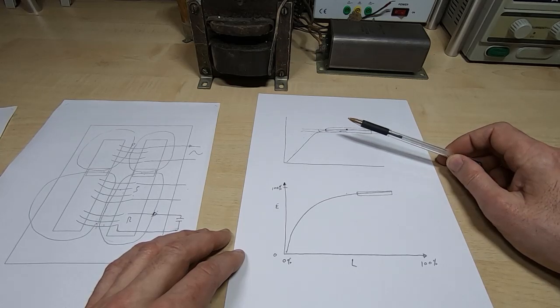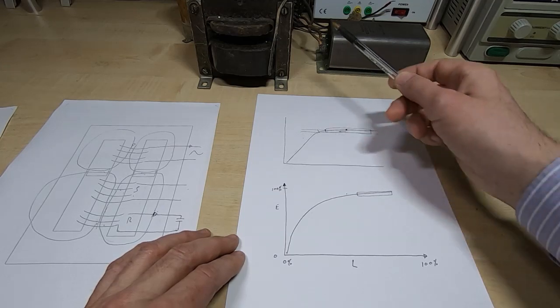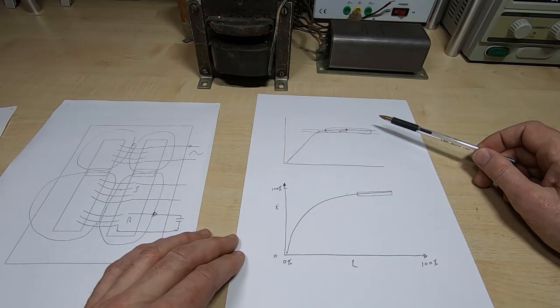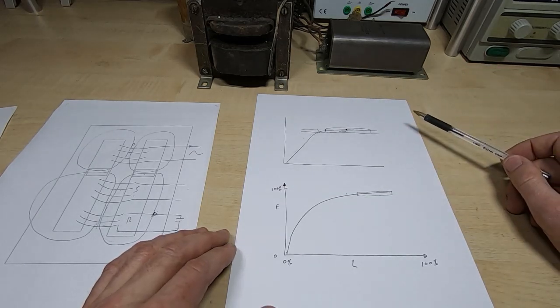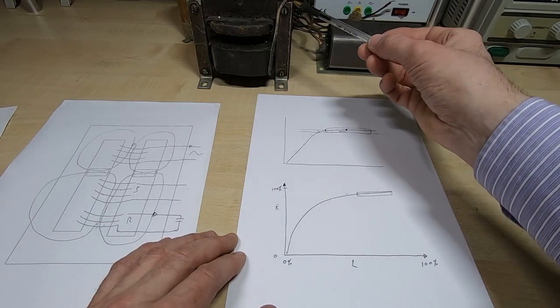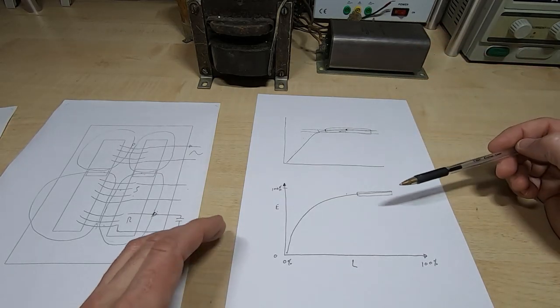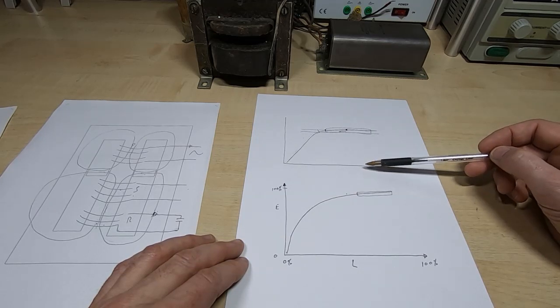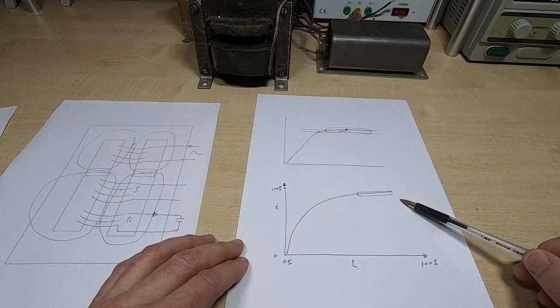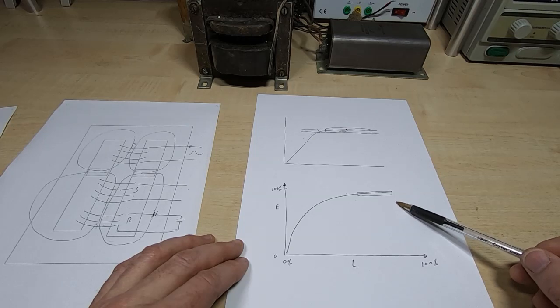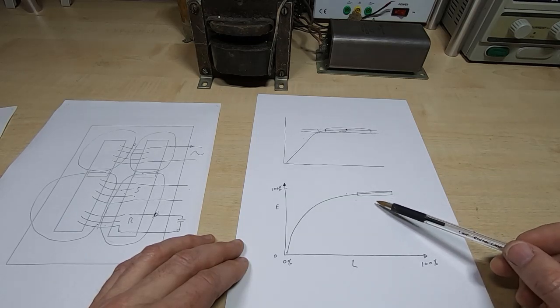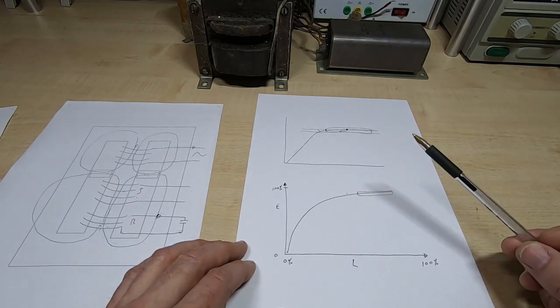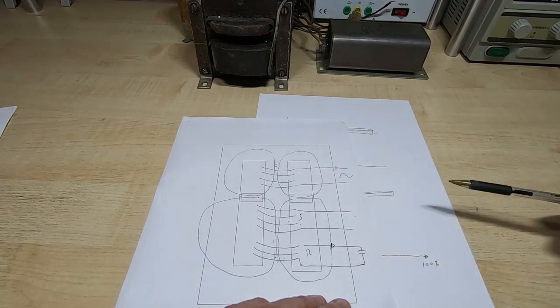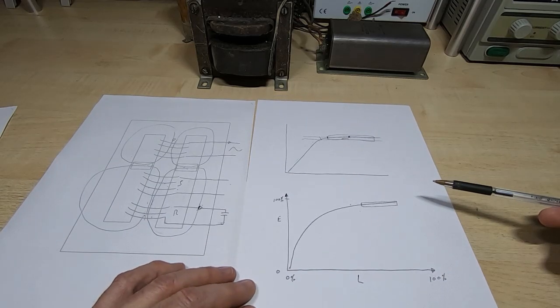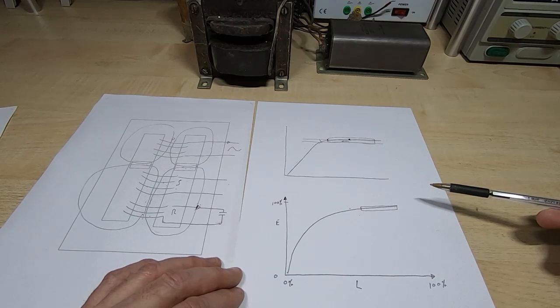Unfortunately, that also means that if you have a highly capacitive load on the secondary, quite often they won't start up properly, because each time they try to start up, that high inrush current causes them to shut down. If you want a transformer driving a high inrush current system, you have to make it a bigger transformer. The problem with making it bigger is that you set its operation point higher up, which means that in normal operation, if there's a high inrush current but a low running current, it will be very inefficient. So it's a balancing act to get their rating correct, to make sure your shunts are properly designed to give the correct coupling between the two parts of the transformer, and also to make sure the transformer is capable of starting up properly in the environment in which you're trying to run it.